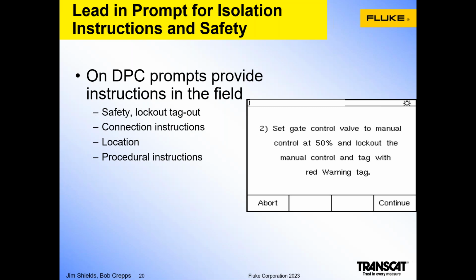Once the task is pulled up on the calibrator, the documenting calibrator can provide lead-in prompts in advance of the actual calibration. For example, walking through a lockout tagout procedure, or information in the procedure to tell the technician where to find the device, how to make connections, or who to call at the control room to babysit this particular loop while the tag is taken offline.